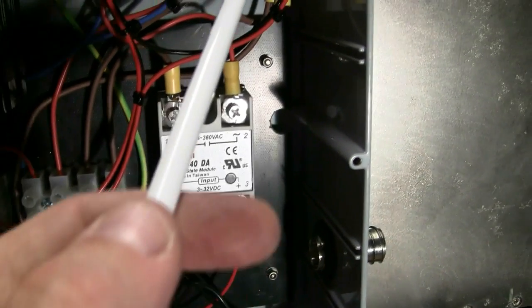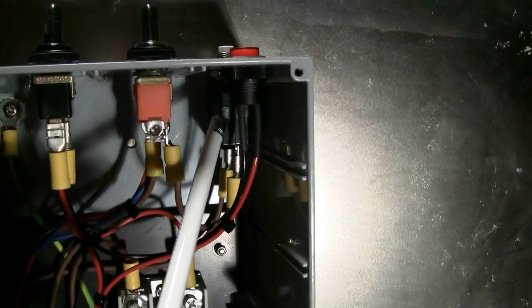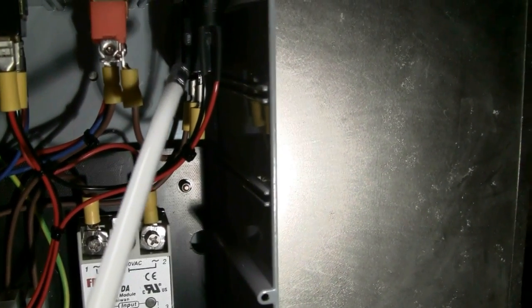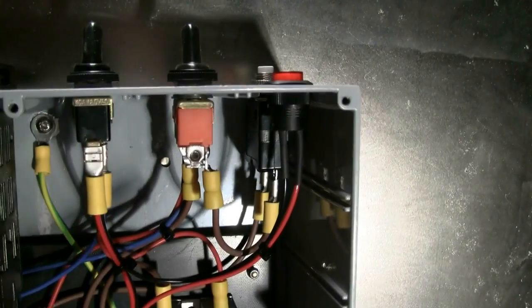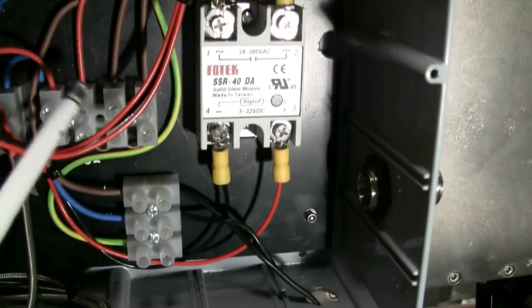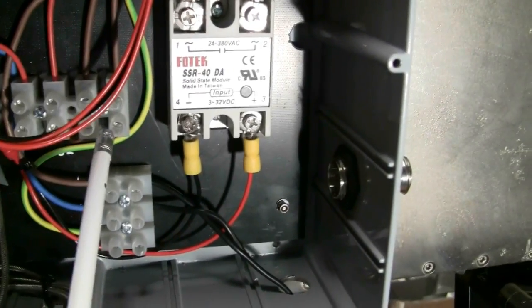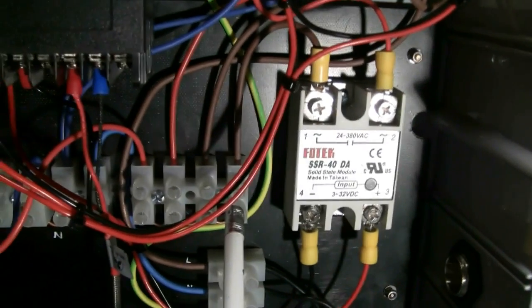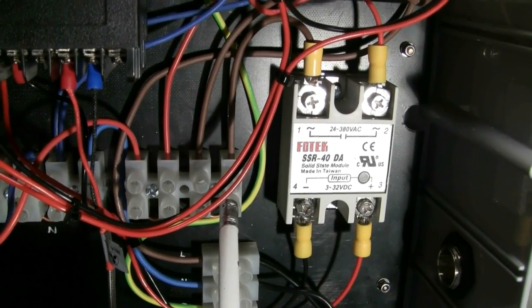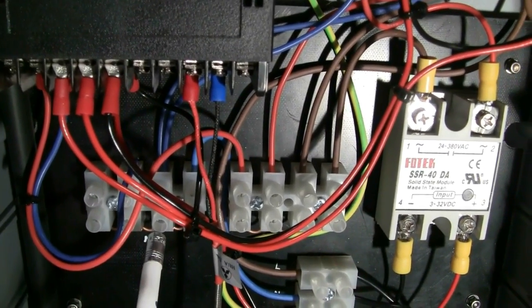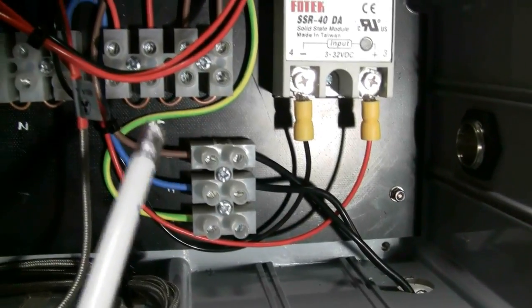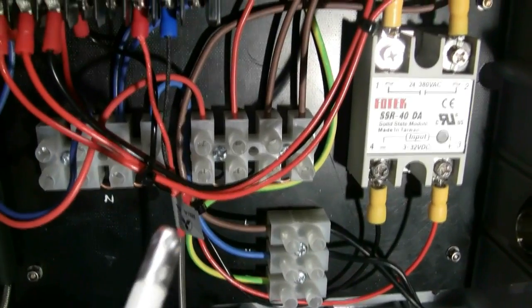It's pretty simple. There's a lot of wires but it's straightforward. The mains live comes in through this circuit breaker, so the mains initially comes in through the circuit breaker before the main switch. There's the main switch, so the protected switch mains comes down to this chocolate block here. This is switched live, and then this chocolate block here is neutral. They're kind of bridged at the bottom so they're all effectively one bus bar.